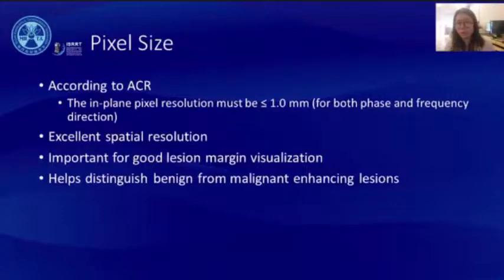According to ACR, the in-plane pixel resolution must be less than 1 mm for both phase and frequency directions. It can be achieved by selecting an acquisition matrix that is large relative to the FOV in both the phase encoding and frequency encoding directions, which will give an excellent spatial resolution. Sub-millimeter in-plane pixels are important for good lesion margin visualization, which helps distinguish benign from malignant enhancing lesions based on their morphology.